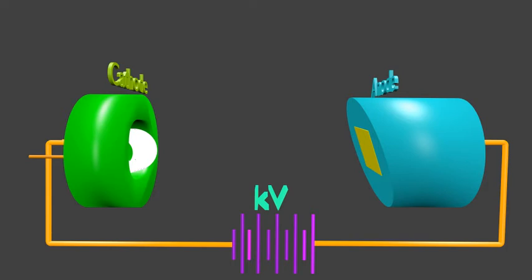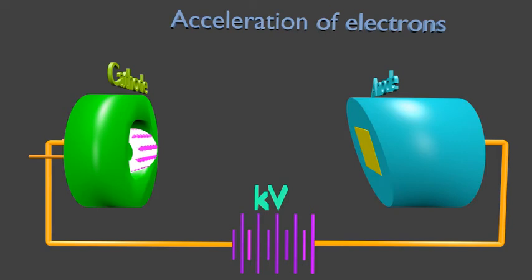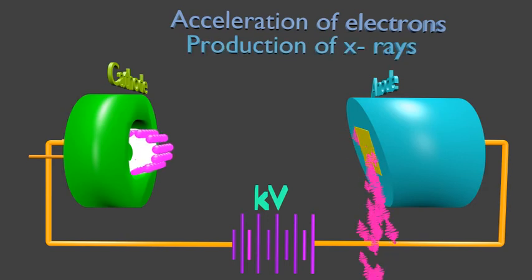The anode of X-ray tube is always kept at higher potential than cathode. Electrons being negatively charged particles are attracted towards higher potential, that is anode here. So electrons produced from filament move towards anode.